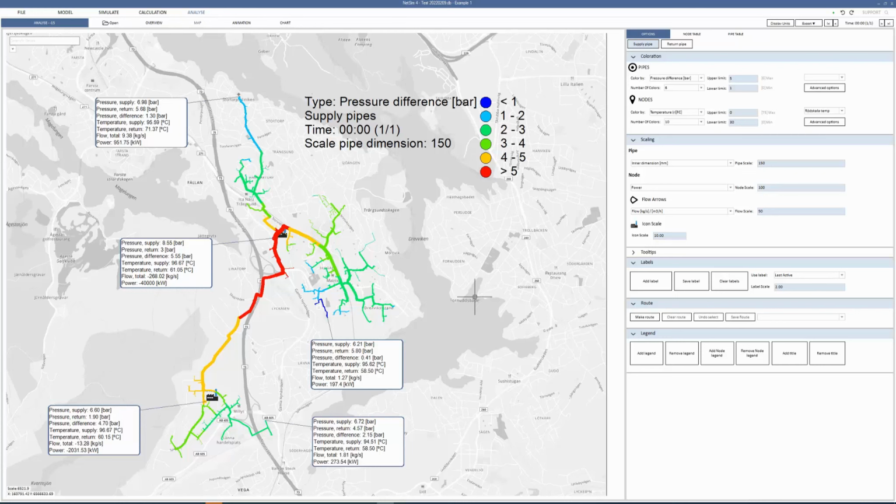And what we're looking at here on my screen is the calculation for a grid outside of Stockholm. So we're just south of Stockholm here. And we have a load case of minus 15 degrees. So this is how the grid is expected to work at minus 15 degrees Celsius. That's not as cold as it gets, but it's the coldest, more stable temperature we get, and that is actually recurring a bit more frequently than the colder minus 20 or so that happens once in a while.